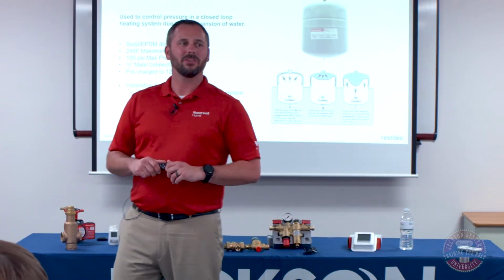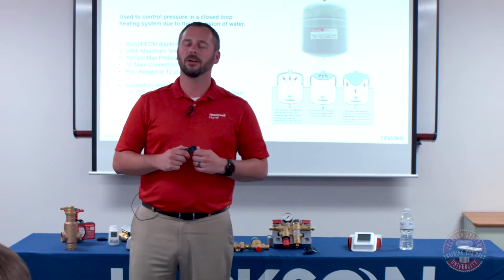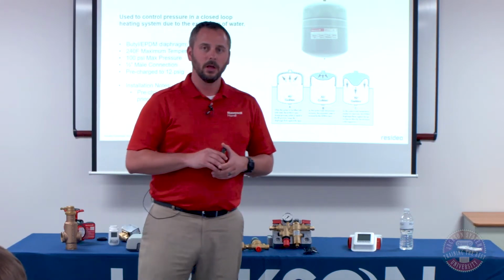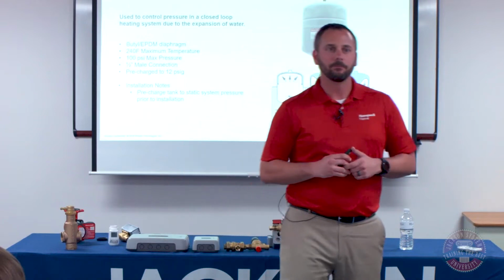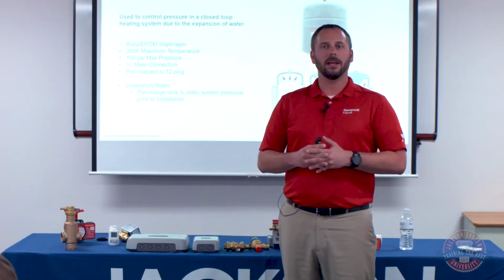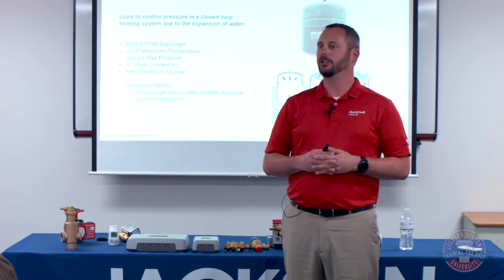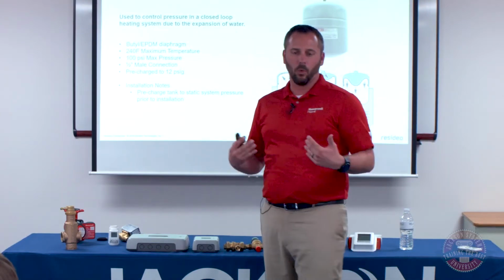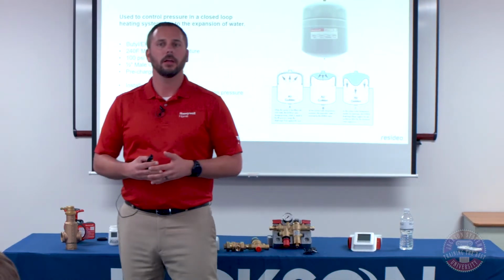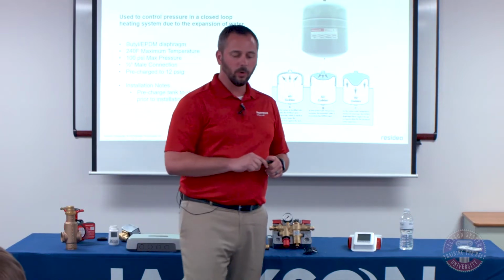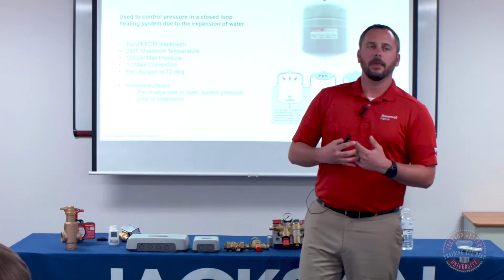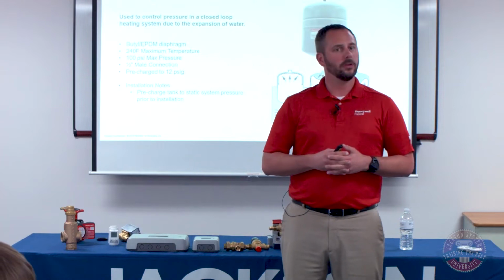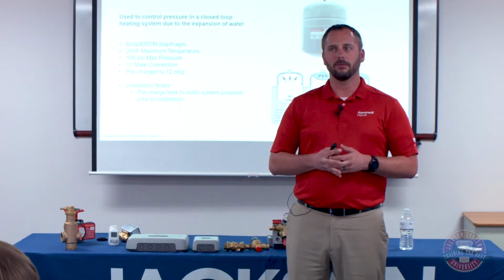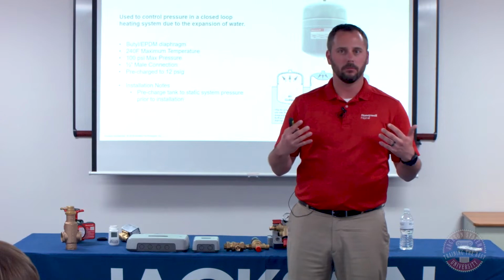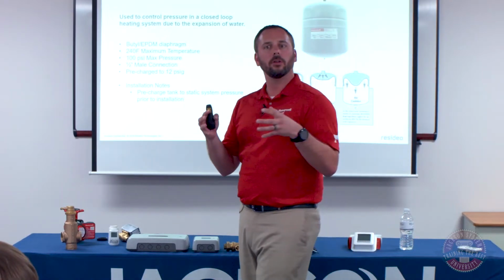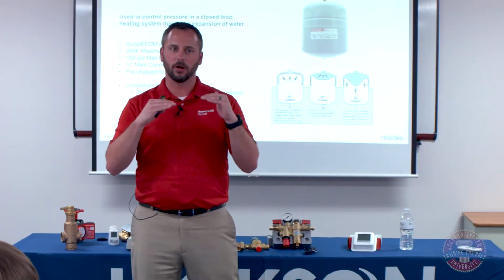So the other component, we talked about filling it with a certain pressure. We talked about backflow devices. Let's talk about expansion tanks. The purpose of an expansion tank is essentially to keep consistent pressure in your system. As water gets hot, it's going to expand. The current hydronic expansion tanks that we sell today are not actually filled with air, per se. There's basically just a welded tank that's got a little diaphragm lip across the top.